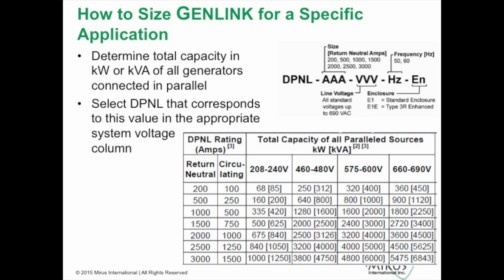So we provide sizing tables to make it easier to select the size of the DPNL for a particular application. The way these tables work is that you total up the capacity of all paralleled sources. So if you have 2 generators being paralleled, you total up the capacity of the 2 generators. If you have 2 generators with a utility transformer, you total up the capacity of the 2 generators plus the utility transformer, either in kilowatts or kVA.